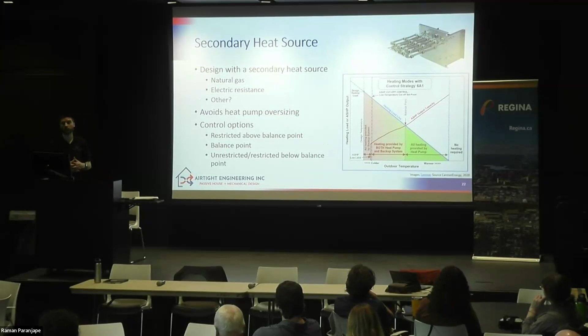The other big design consideration I'd highlight is that heat pumps are different from fuel-fired appliances in that their capacity changes with outdoor temperature. If it's -30 outside, it's a lot harder for that heat pump to pull heat from outside than if it's -5. Whereas a furnace rated at 60,000 BTUs puts out 60,000 BTUs no matter the temperature.